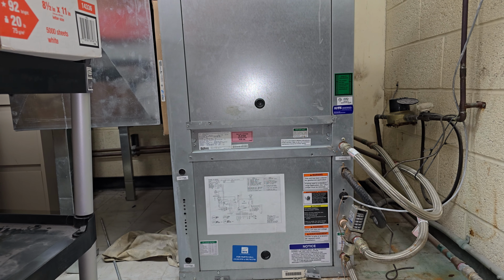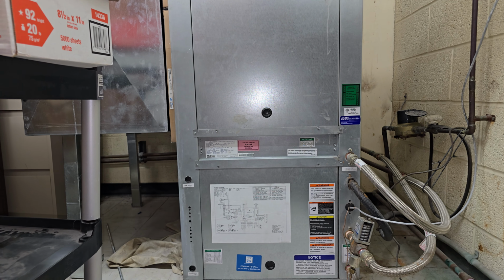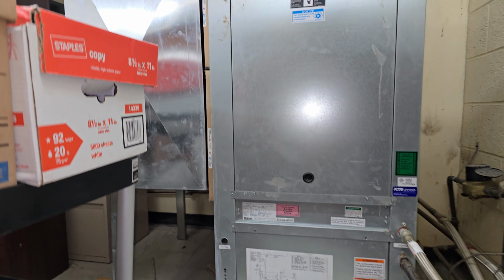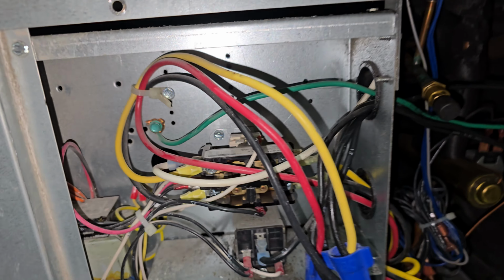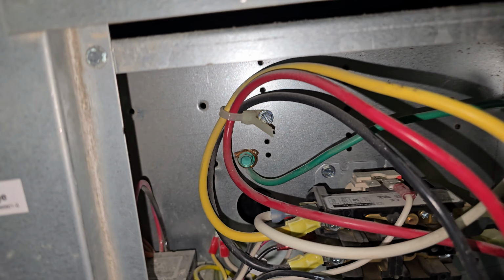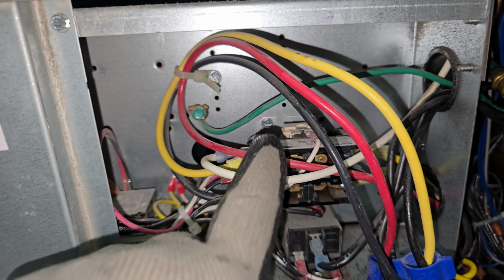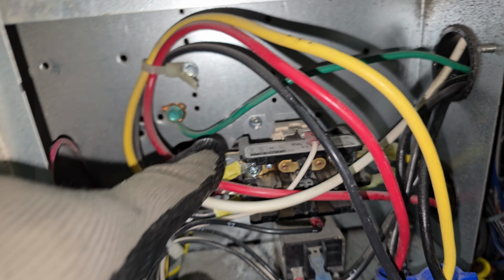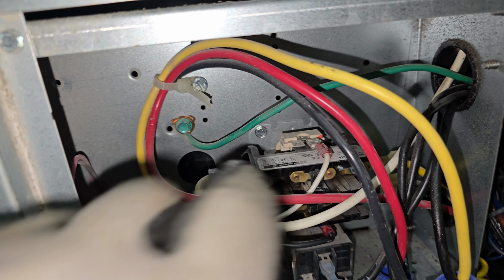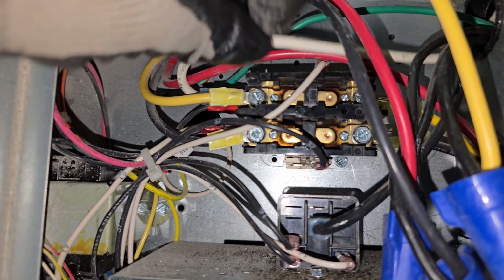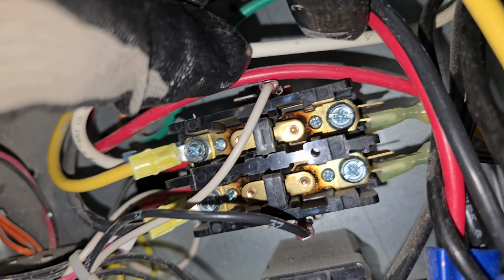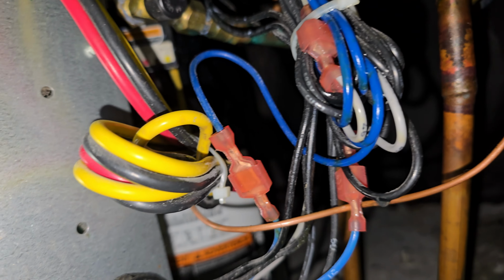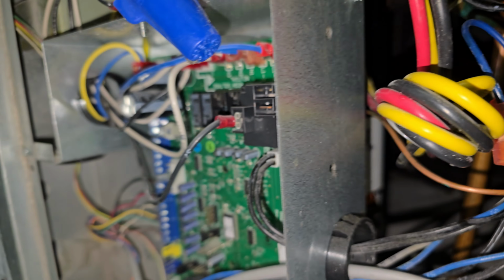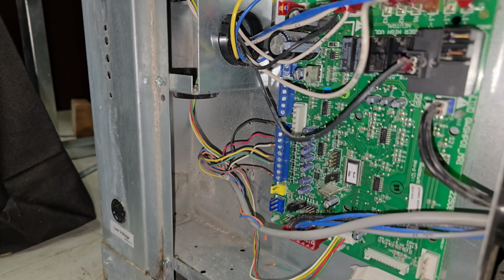Okay, so we came back with the parts to get it fixed. So we'll keep it posted. Okay, so we'll be replacing this contactor first. And then after replacing this contactor, hopefully our compressor comes on really well. You can see the contactor is really bad. And if our compressor comes on well, the compressor has been turned off for a while, so it's also cooling off. So I have a new contactor here.